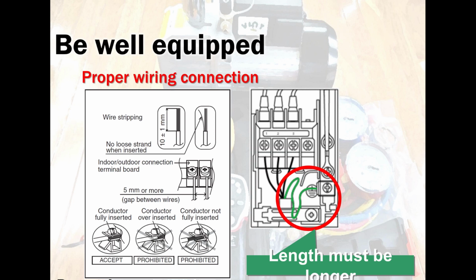Wiring. Wiring is so crucial, guys, especially the control wire that is running from indoor to outdoor. The communication wire, 1, 2, 3, and ground, should never ever be joined in between. Never cut that wire and join in between. Always get a full cable, a complete cable, end to end. I get guys calling me and saying, Paul, you told me not to cut wires. I had no choice. I had a short wire. I cut it and it's running fine. And you told me not to cut. It will not work. I told him, hold on.